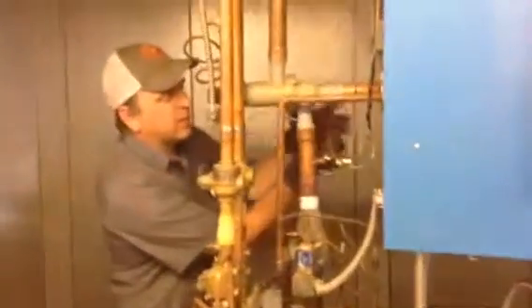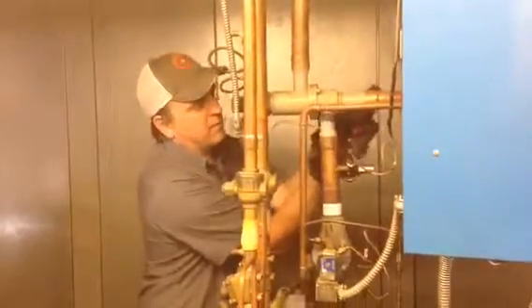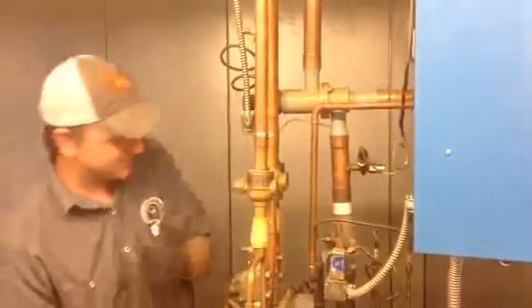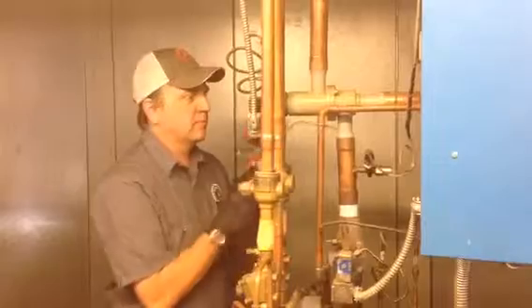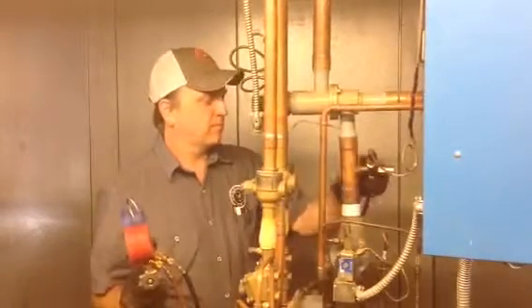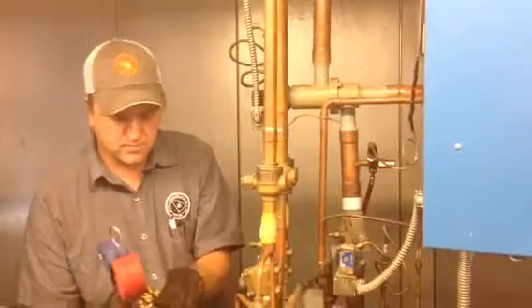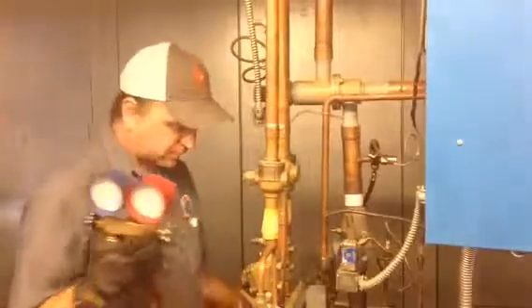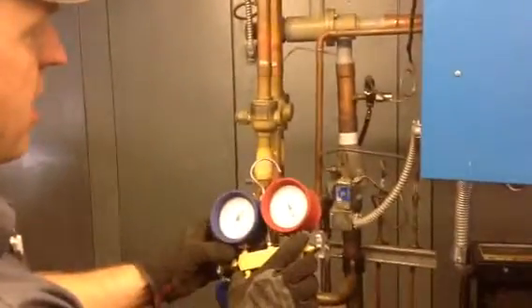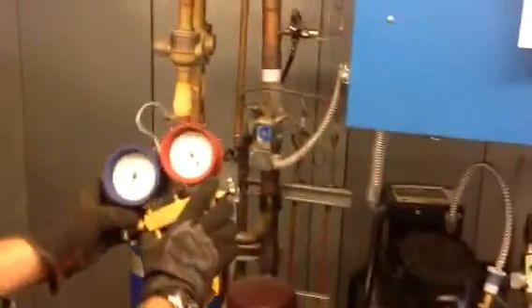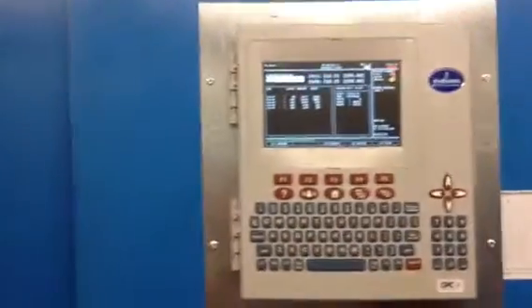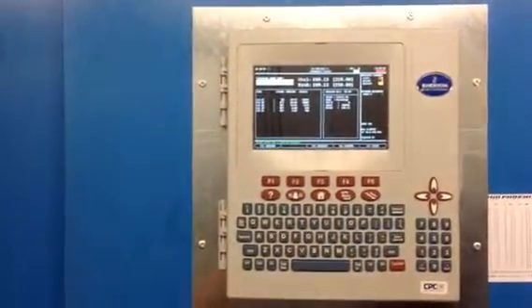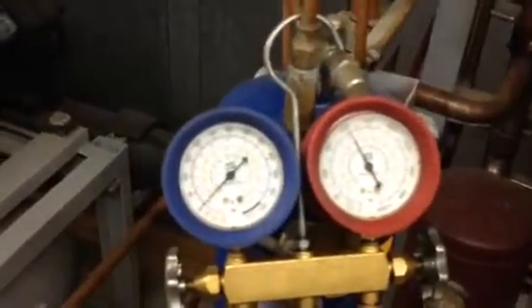Take a pair of pliers. Rocky had that one on tight. Check your pressure. This one's showing about 215 pounds. So we go to our rack. We have 210 pounds. We're going to let that settle for a second because the condenser fan is on. Check our gauge one more time. Let's make sure we didn't drop. Which we did. We have about 205 pounds.